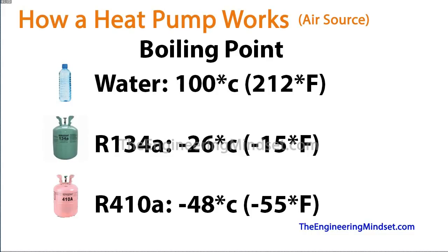Now the reason you can extract thermal energy from the air, depending on the temperature, is because the boiling point of the refrigerant is very low. So if we look at water here, as we know, water boils at 100 degrees Celsius or thereabouts, at about 212 degrees Fahrenheit.